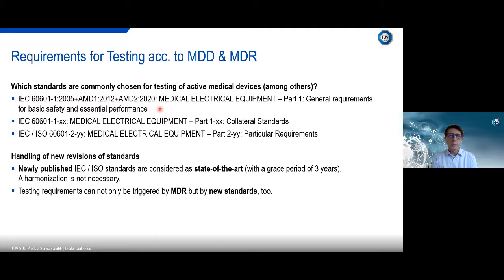Together with this basic standard, we have the so-called collateral standards, where the number is 60601-1-XX, where, for instance, specific requirements for alarms or for, let's say, medical devices used in the home healthcare environment are documented. And in addition, the third part of this family are the so-called particular standards, the particular requirements for specific products. They are documented in the IEC/ISO 60601-2-something.